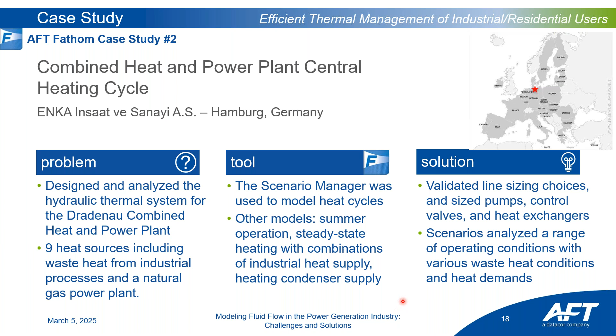They talked about some of the cases they got into. What they were able to do on this new design is validate line sizing choices. They sized pumps, control valves, and heat exchangers, and used the scenarios to analyze a range of operating conditions with various waste heat and heat demands.